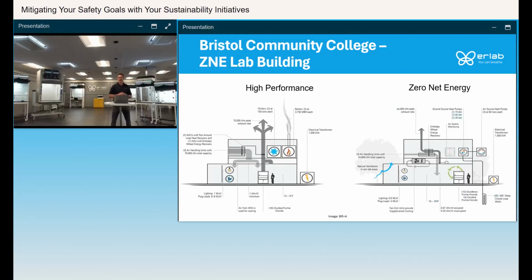Problem was, if they had the 18 ducted fume hoods, they had 2 5-hood chemistry teaching labs. You saw from the previous example, that's going to be about 14, 15 air changes per hour. And they were like, we need to go ductless. And by going ductless, they were able to eliminate 1 complete air handling unit.